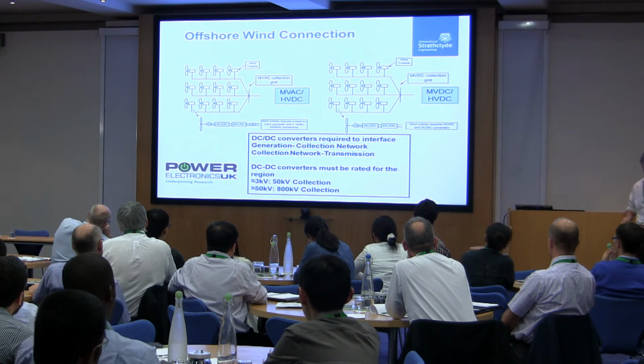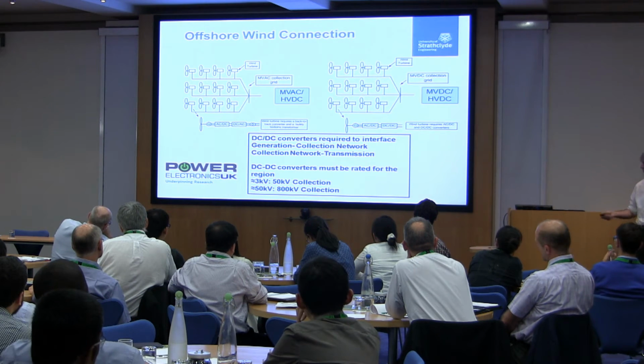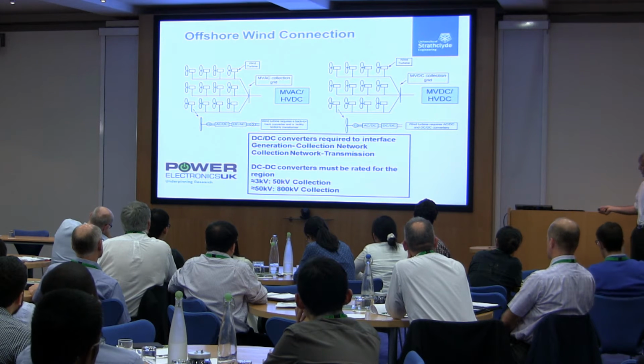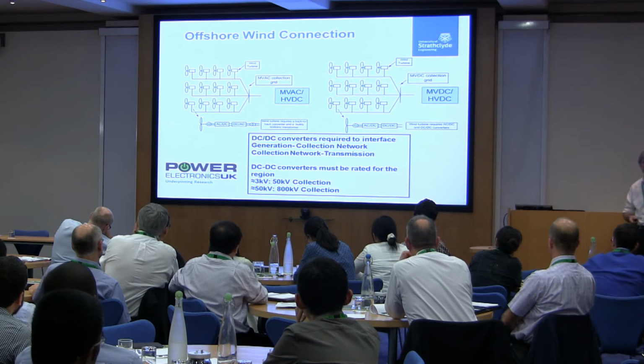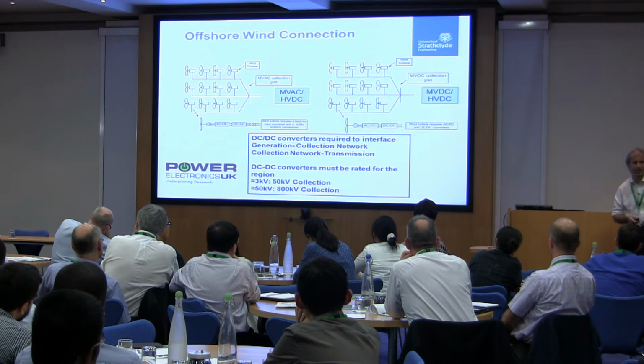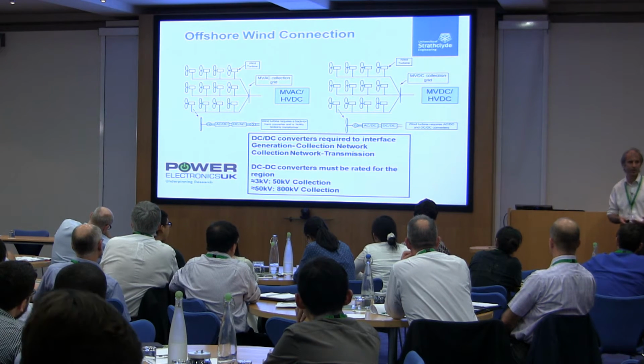It's unlikely that the appropriate voltage for the wind turbine DC bus would be the same as that which we'd have to have in our collection network. So we might be, for a high voltage machine, 3 kV, maybe a bit higher for the machine bus voltage, and we'd want to probably step up to maybe 50 kilovolts. I'm not saying that's precise, but that's the kind of area where we need to get that step-up ratio.